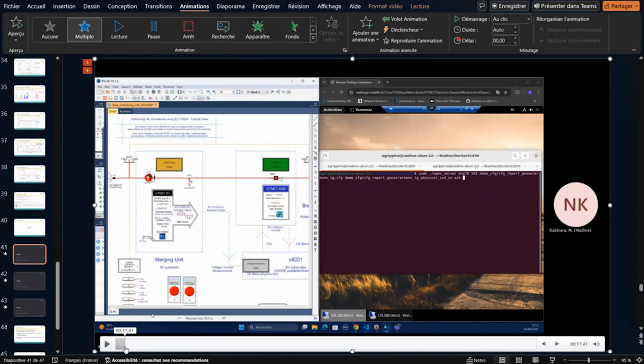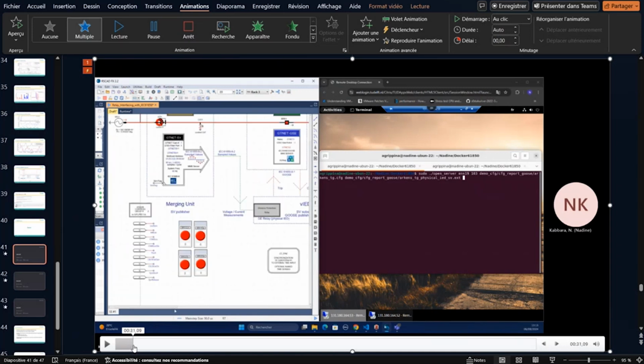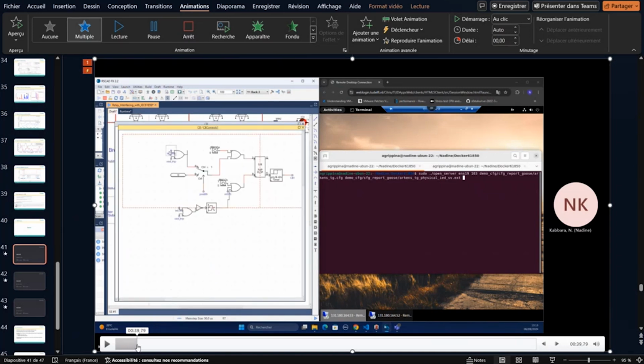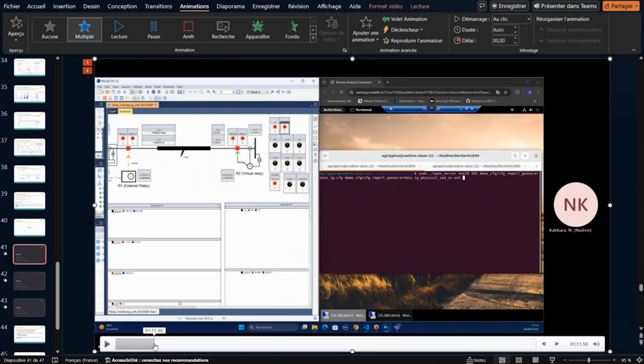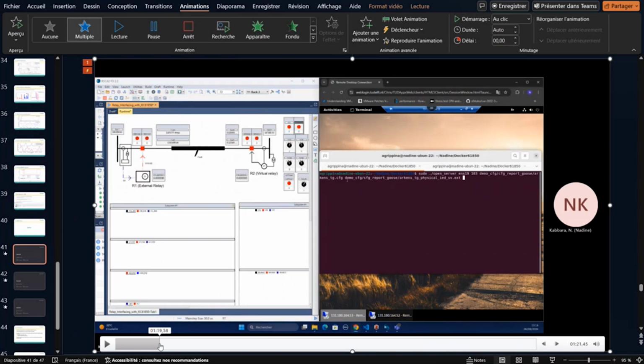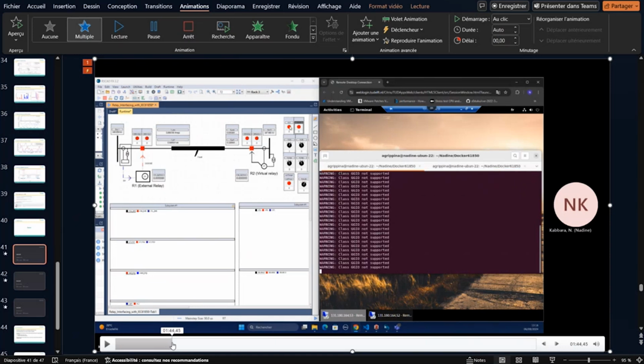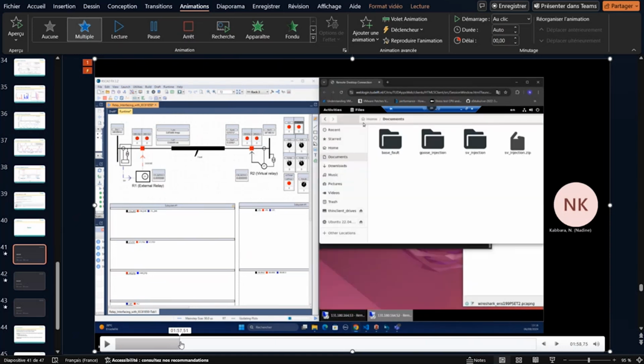I will quickly show you the environment where we were able to do the attack. To the left, you see the RTDS 5-bus model configured with the sample value and goose networking cards, and the IEC 61850 goose to trip the signal, receiving the tripping signal and subscribing to the physical IED and virtual IED goose trip inside the RTDS model as a subscriber. In the model, we could also simulate all the currents, voltages, and faults.